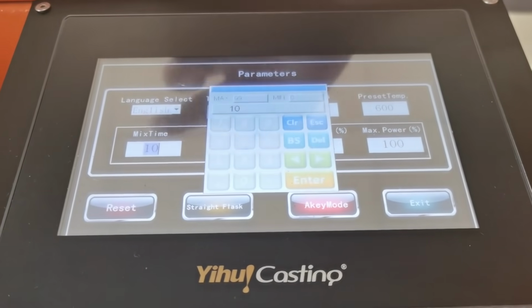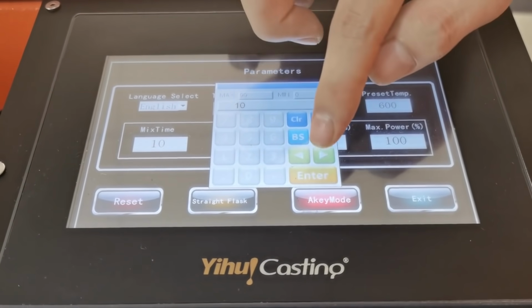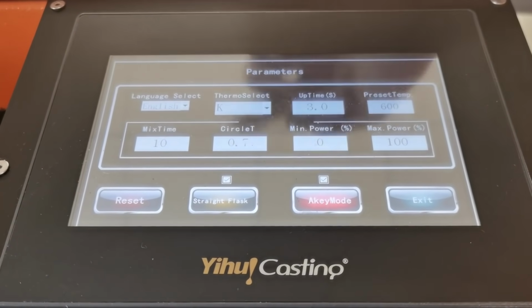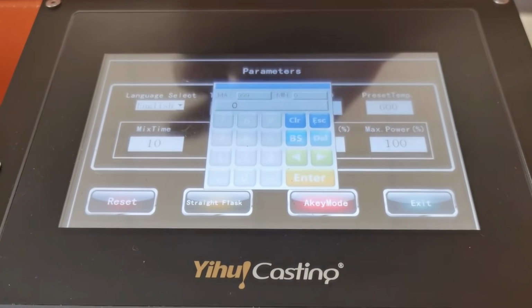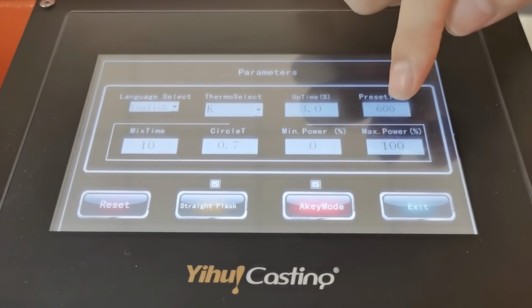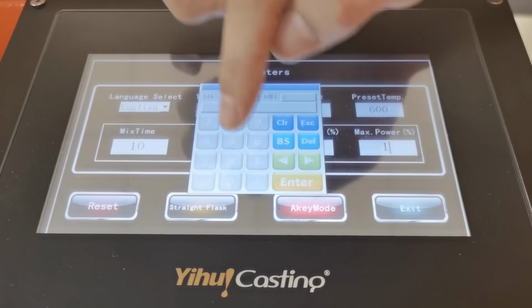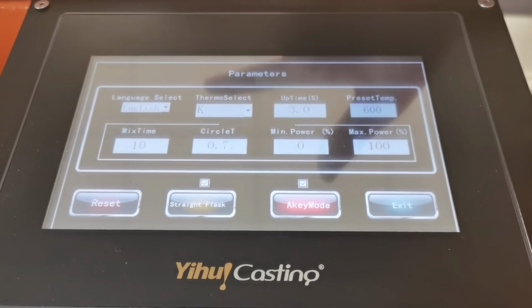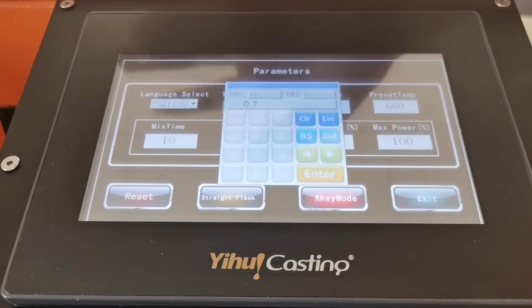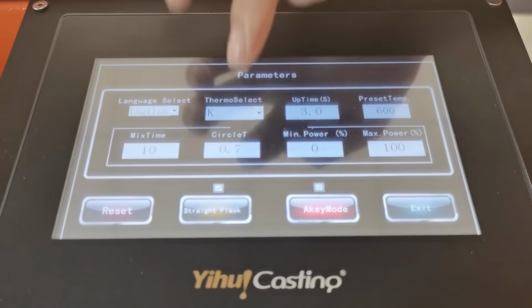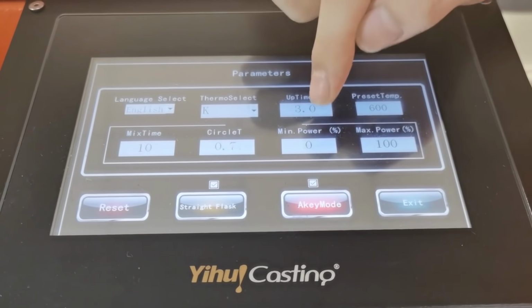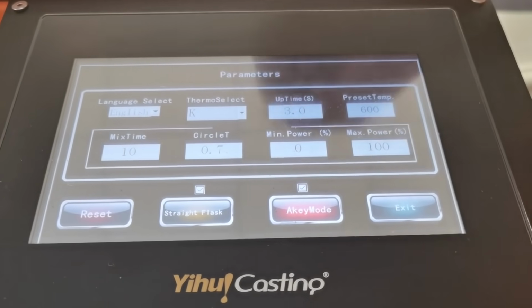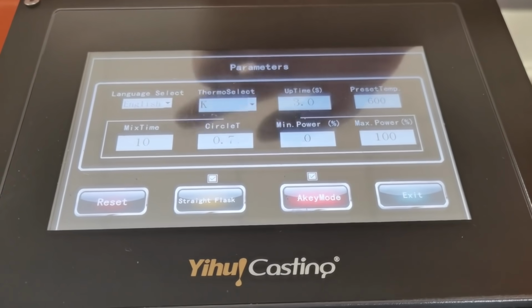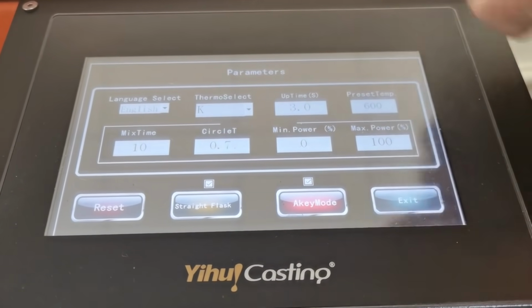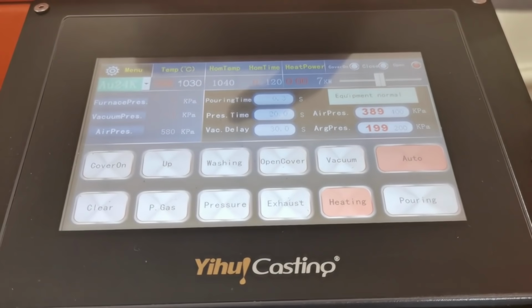Then turn to the mix time. Mix time we set as 10 seconds. Then turn to the mini power and the max power. For the mini power, we set 0%. For the max power, we set 100%. At last, we set the circle time. Circle time we can set as 0.7. This time means when the system power comes to the mini power and the max power, the system will stop for 0.7 seconds. After finishing this, we press exit to set the temperature.